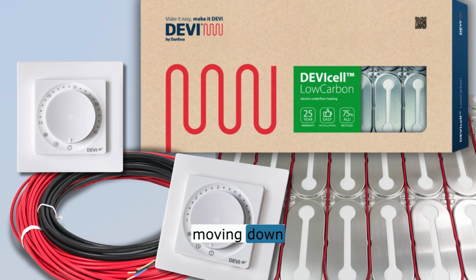Got it. Now, moving down the power line, the manuals give us these specific requirements for fuse sizing, which is based on the thickness of the wires. Yes, the cold leads. Right, the cold leads. So that's the non-heating power wire that runs up your wall to the thermostat. It says if your cold lead is 1.5 square millimeters thick, you're restricted to a 10 or 13 amp fuse. But if you upgrade to a thicker 2.5 square millimeter lead, you can use a 16 or 20 amp fuse. Why such strict matching? It all comes down to thermal limits.